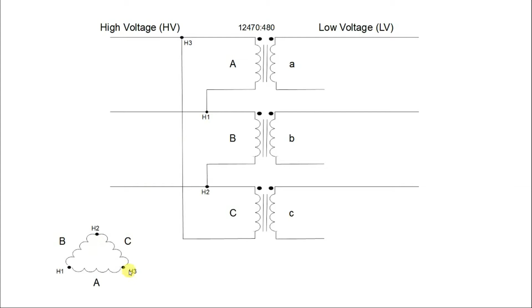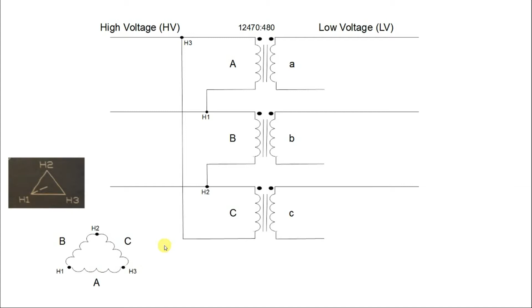My A phase is between H3 and H1 - if you look between H3 and H1, there's my A phase. My B phase is between H1 and H2, which we see here, and my C phase is between H2 and H3. This little snippet of the faceplate shows the exact same configuration: H1, 2, and 3 for my three delta connections.